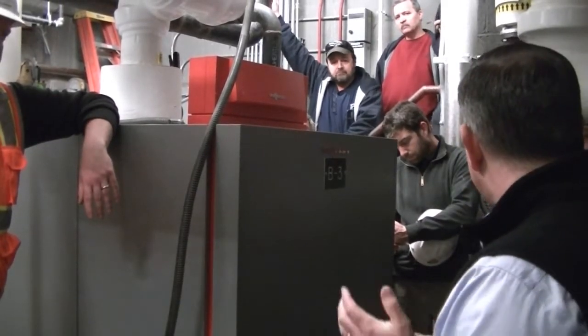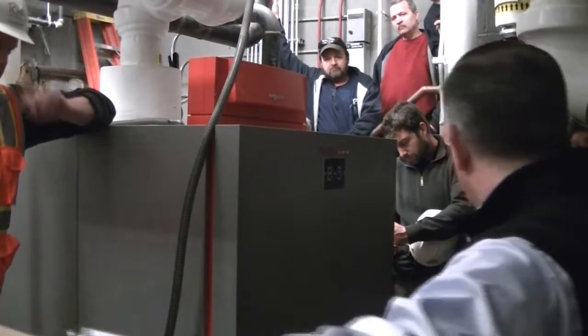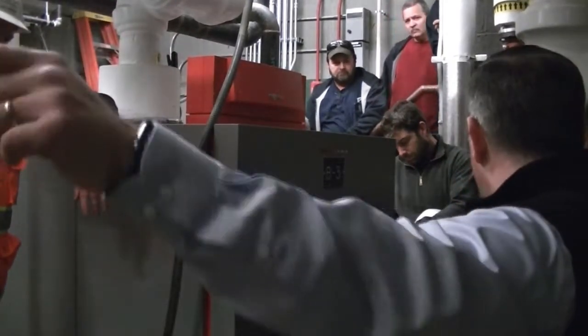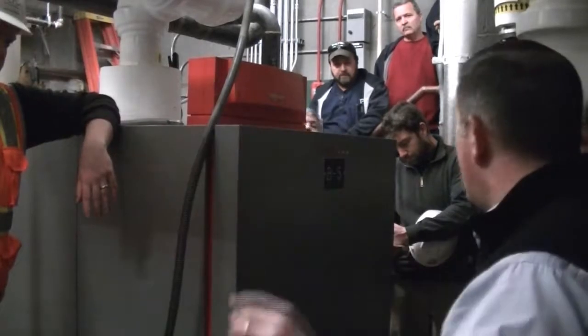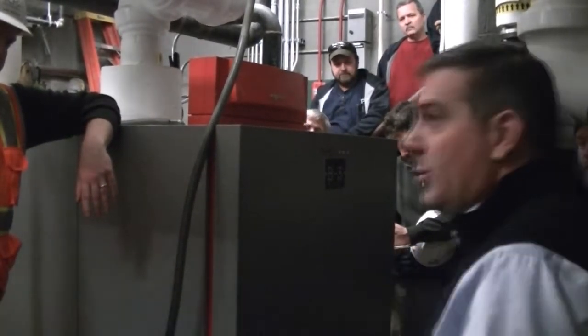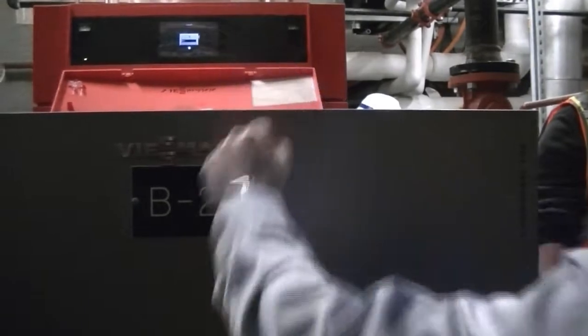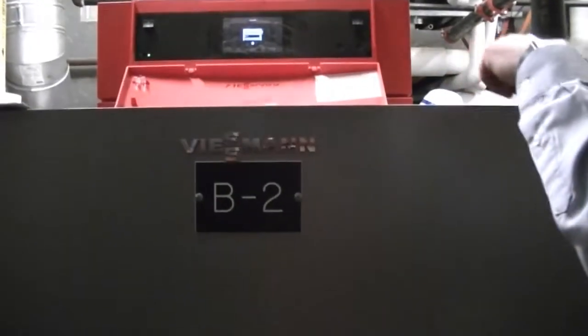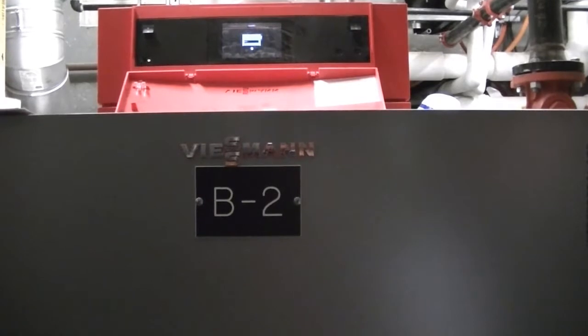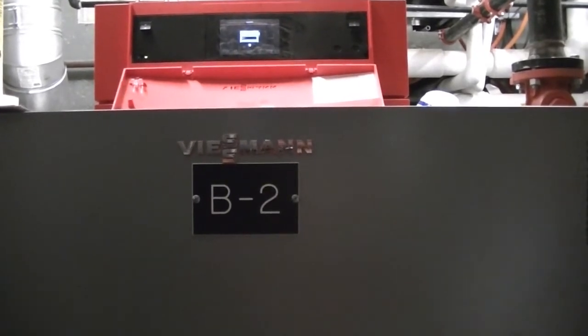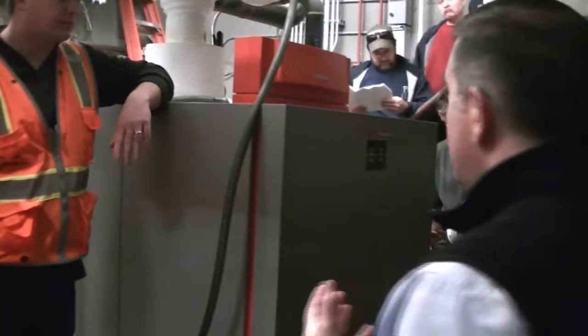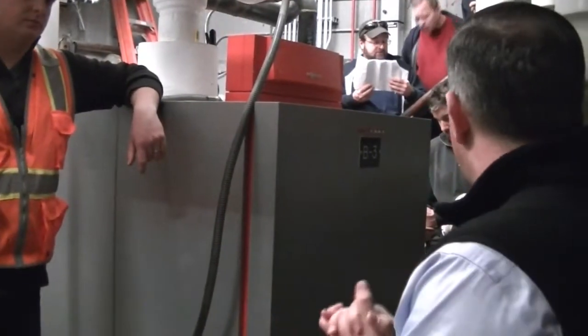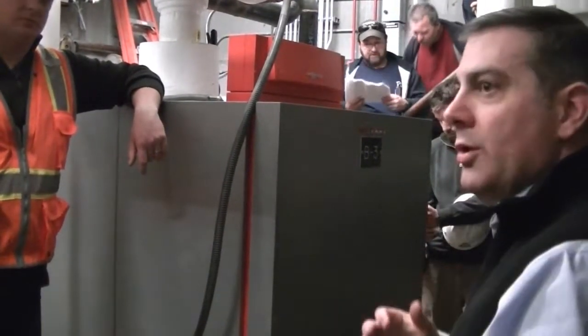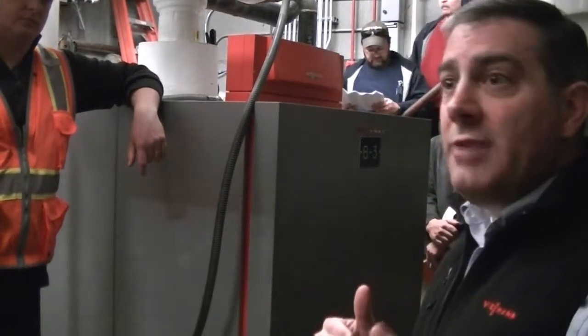If you didn't have the cogen, it would be boiler 1. Boiler 1 would be boiler 1. So if you look at our system, it's still labeled as boiler 1. So if you see the boiler 1 tag on our control, it's still reading our boiler 1. If you open this control here, even though the jacket panel on the front of the thing has a label that says boiler 2, the screen actually says boiler 3. So realistically, you've got 1, 3, 4, and 5 up top, and boiler 2 is actually the cogen system on top. Right? So after the lead boiler has run and either gotten the temperature up to where it's supposed to be or not satisfied the load, the next boilers will start to come on in a cascade fashion.